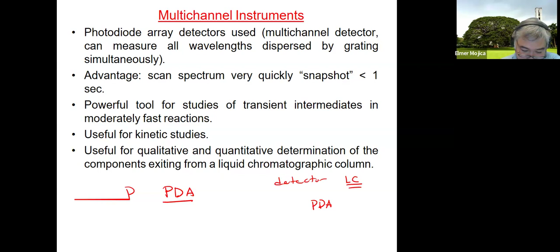So if you're going to look at this, what we call composition of this photodiode array, so this is the diagram of a multi-channel spectrometer based on a grating spectrograph with an array detector. So this is the spectrograph that you have there, the grating. So you have the source, it could be D2 and W. Okay, so the radiation from the tungsten, so the deuterium source is made parallel and reduced in size by the lens and the diaphragm.